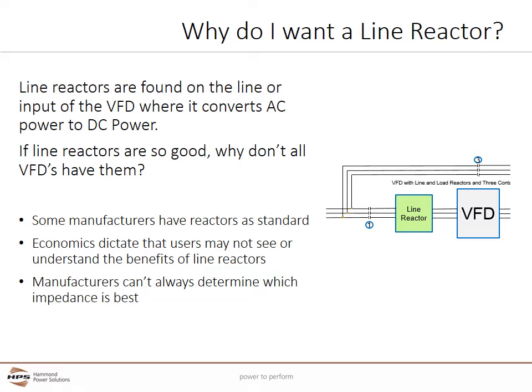Line reactors are found on the line or input of a VFD where it converts AC power to DC power. If line reactors are so good, why don't all VFDs have them? Some manufacturers actually do include line reactors as standard in their VFDs. Economics also dictates that users may not see or understand the benefits. Additionally, manufacturers can't always determine which impedance is best. There are situations where a line reactor isn't just suggested but is truly needed.